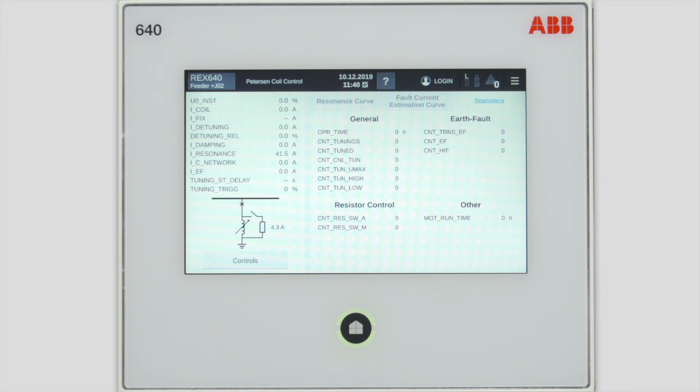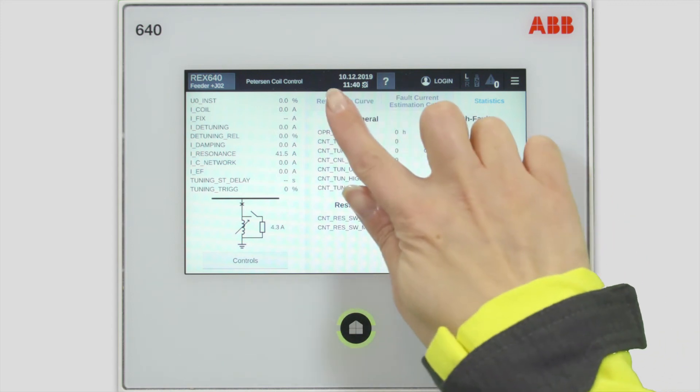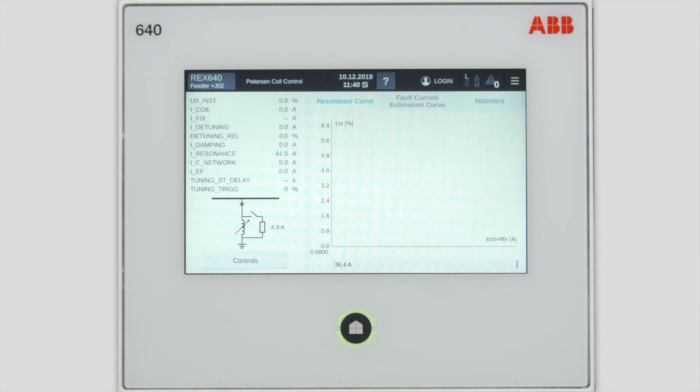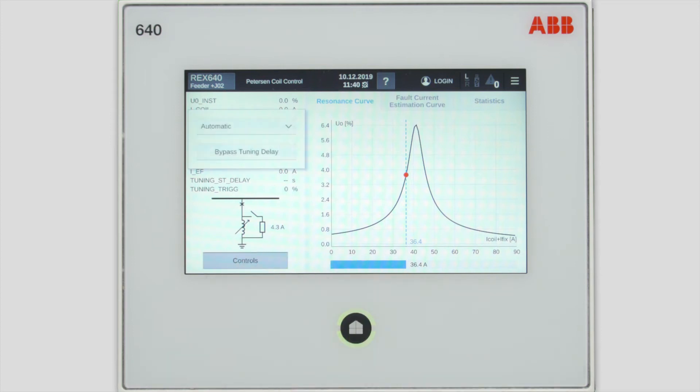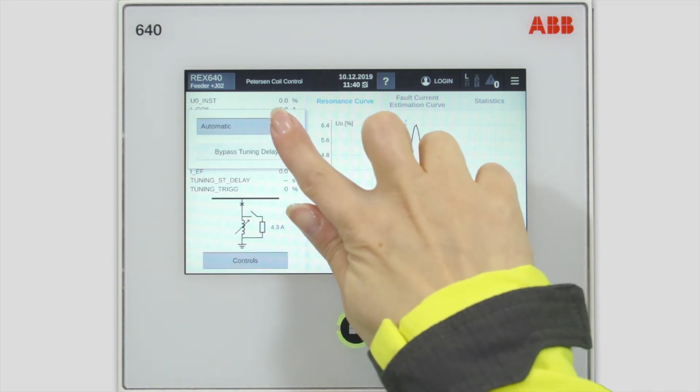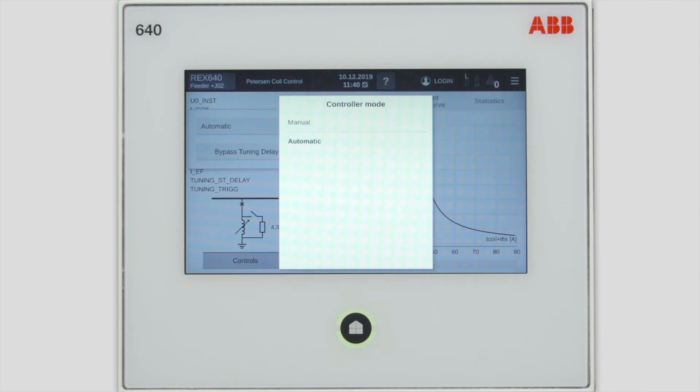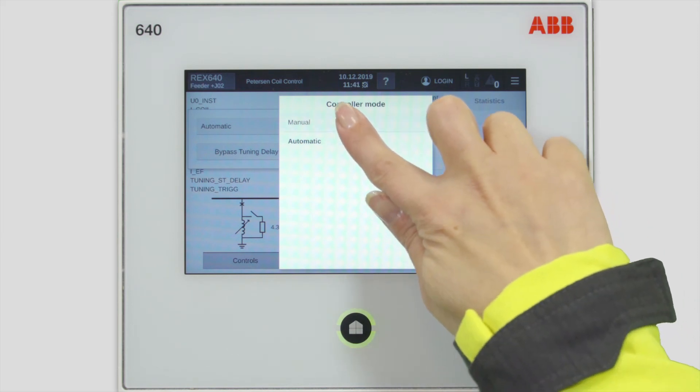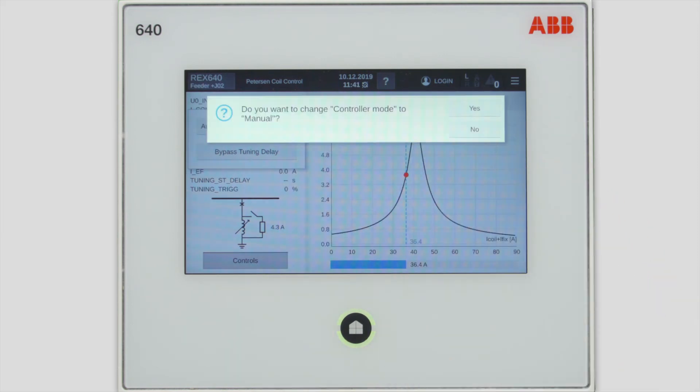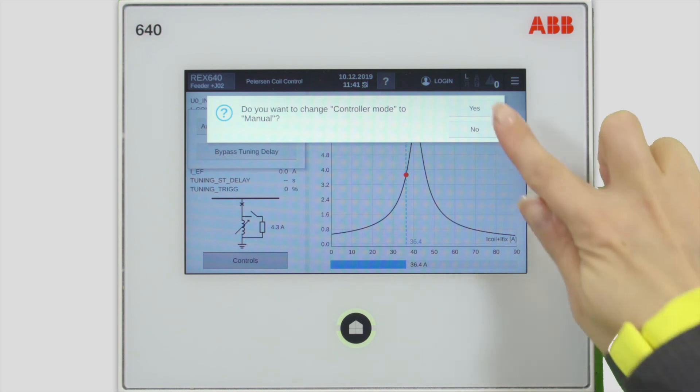Let's go back to the first window, the resonance curve, and choose controls. There are two possibilities for the control, manual mode and automatic mode, which means that the functionality in the relay will automatically control the position of the Petersen coil as per the preset parameters. Automatic would be the normal mode of operation, but let's take a look at the manual mode and confirm the selection.